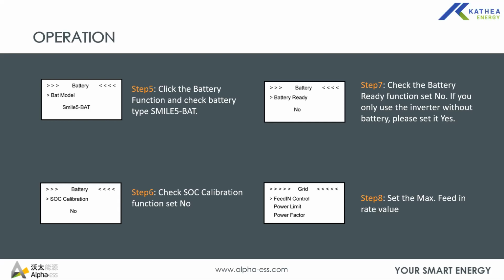And then the next setting after battery is grid. Usually on grid, it will automatically pick all the grid values, the power factor and the frequency, from the grid it is connected to. The only major setting that we need to set here is the feed in. So if you access grid, go to select feed in control. It will prompt you for a user value, which is the maximum power, in percentage of the inverter rating, you would want to feed to the grid.